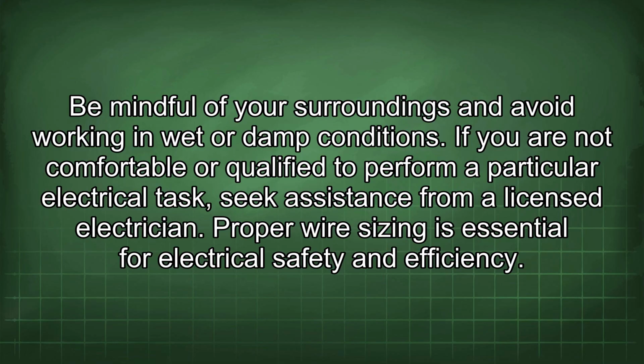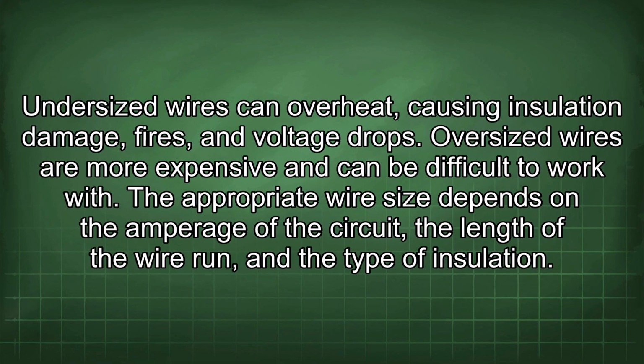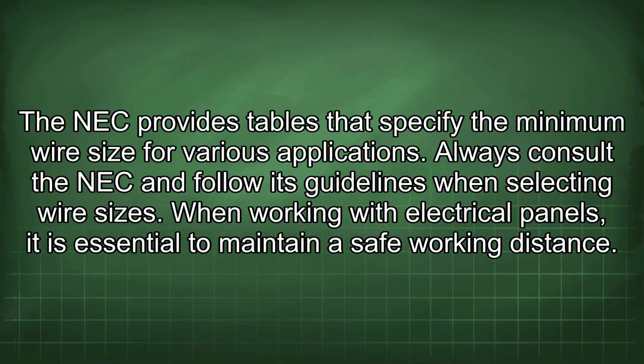Proper wire sizing is essential for electrical safety and efficiency. Undersized wires can overheat, causing insulation damage, fires, and voltage drops. Oversized wires are more expensive and can be difficult to work with. The appropriate wire size depends on the amperage of the circuit, the length of the wire run, and the type of insulation. The NEC provides tables that specify the minimum wire size for various applications. Always consult the NEC and follow its guidelines when selecting wire sizes.